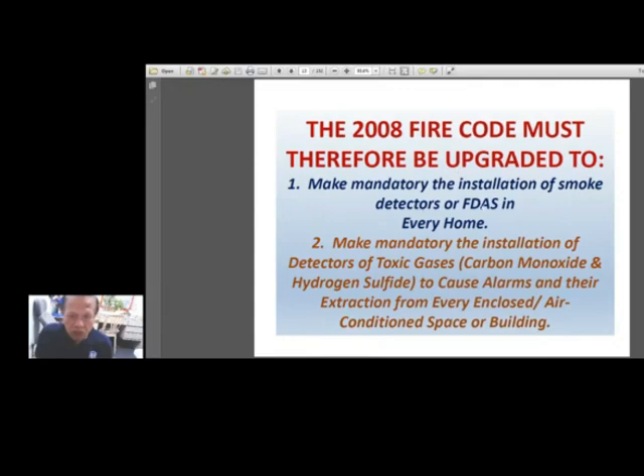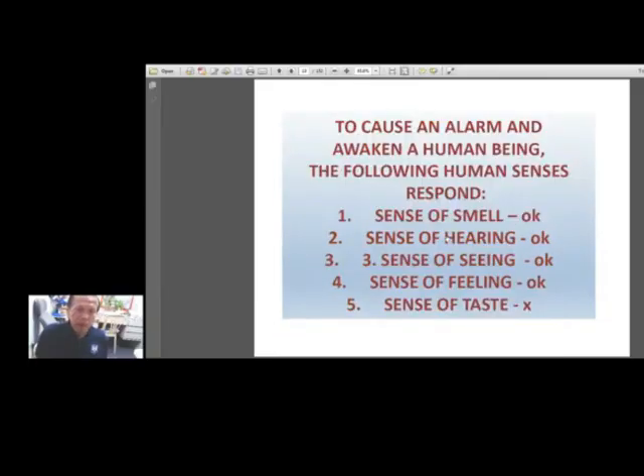So let's repeat. Number 1 suggestion is to make mandatory the provision of FDAS, fire detection and alarm system, in every home, not only in office or commercial buildings. And number 2, to make mandatory the installation of toxic gas detectors, alarms, and extraction system. So these are not yet in there. It's not also in the NFPA yet. Only number 1 is in the NFPA, except that in the IRR, it is not very strict when it comes to every home. Okay, so let us analyze our present design of the fire detection and alarm system.